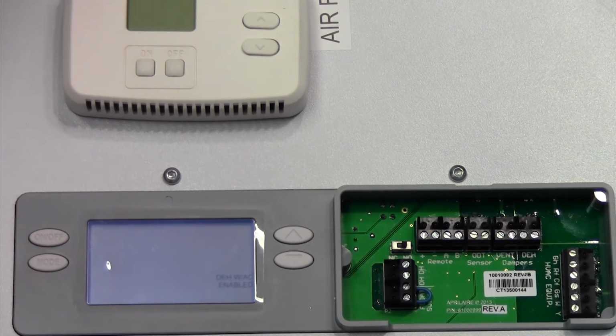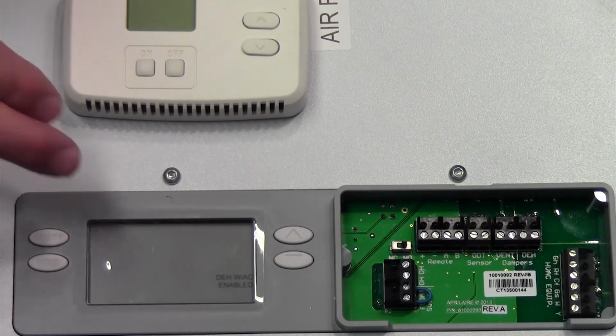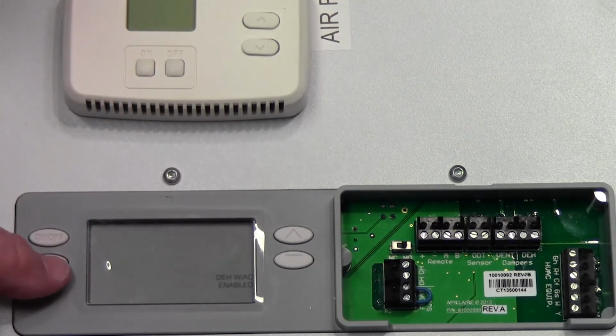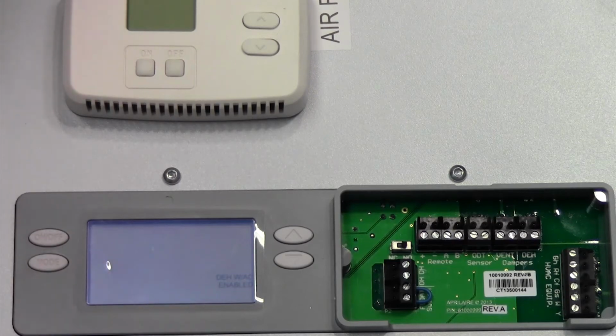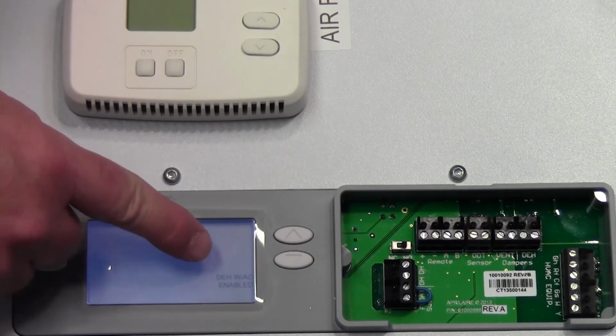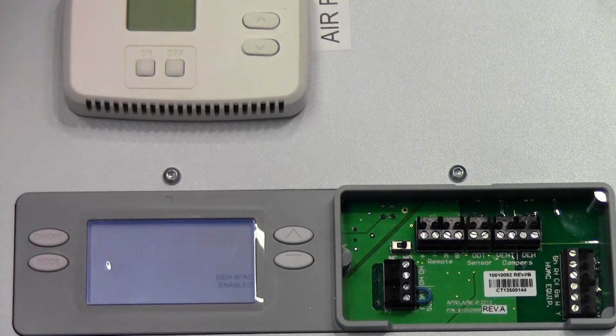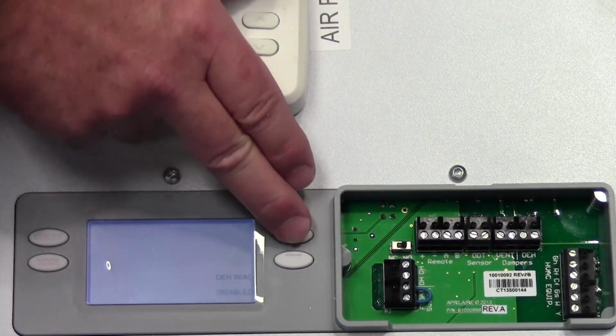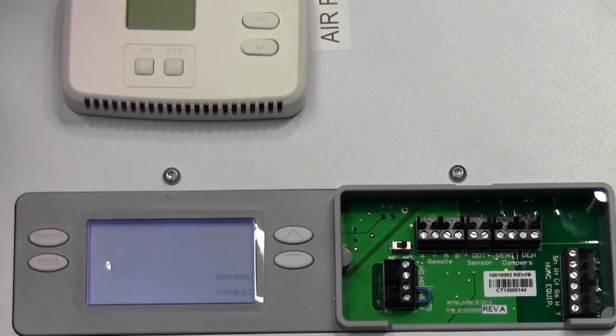The next new feature that we've added to this, we've had contractors ask us for a way to disable the dehumidifier when the air conditioner's on. They don't want them running together for whatever reason. So we set that from the factory as being enabled, so it says DEH, dehumidify with AC enabled. So if you say that together, it means the dehumidifier will run with the air conditioner. But if we choose not to do that, we can disable it, and now the dehumidifier with AC has been disabled, and the dehumidifier will shut off every time the air conditioner comes on.